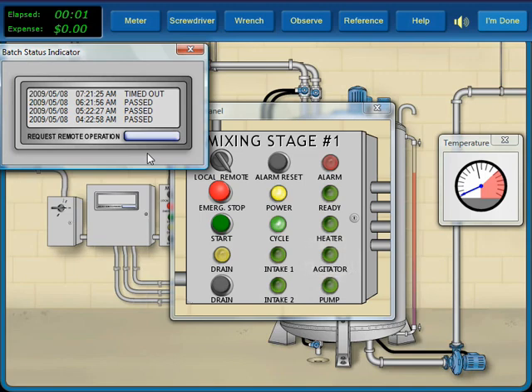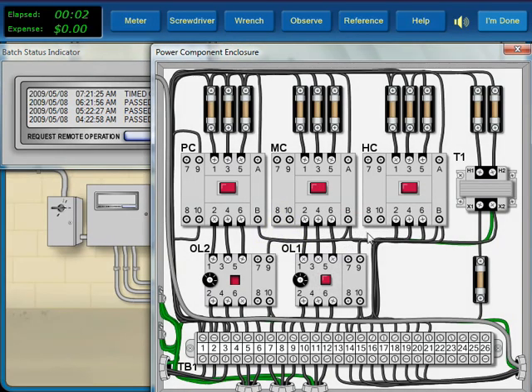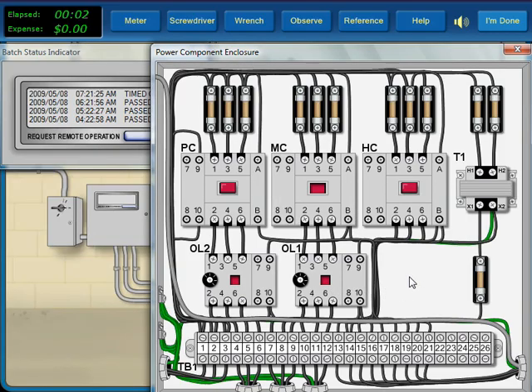Inside the power box, we see that the agitator's overload is tripped. Resetting the overload causes the agitator contactor to pick up, but the overload trips again after a few seconds.